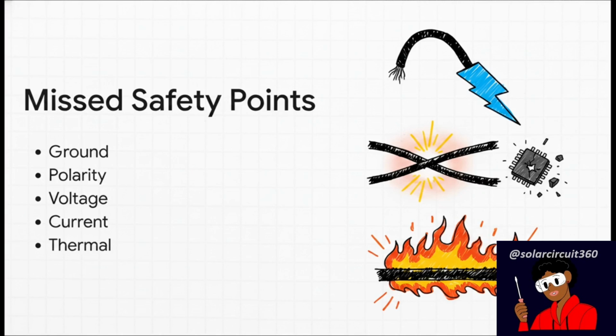Or think about DC polarity confirmation. So many systems are energized without anyone ever verifying the polarity of the MC4 connectors out on the solar panels. A reverse polarity mistake there can instantly blow the inverter electronics and release the dreaded magic smoke. Plus, skipping independent current verification or voltage drop measurements means undersized cables and poor crimps just go completely unnoticed. That is, until they start a fire.